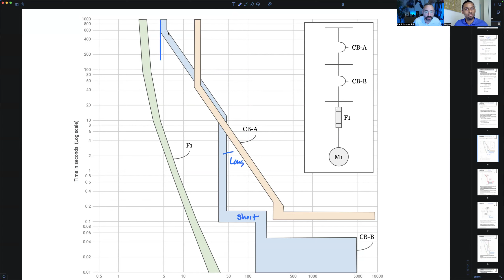So here's the short time region—this leading edge is the tap setting for short time. Whatever the value is on the horizontal axis would be your tap setting, your secondary pickup setting, for your ANSI 51 inverse time overcurrent relay, where this is like a moderate inverse or definite inverse curve—it's almost perfectly flat. So if I trace this, let's see if we can clear that overlap.